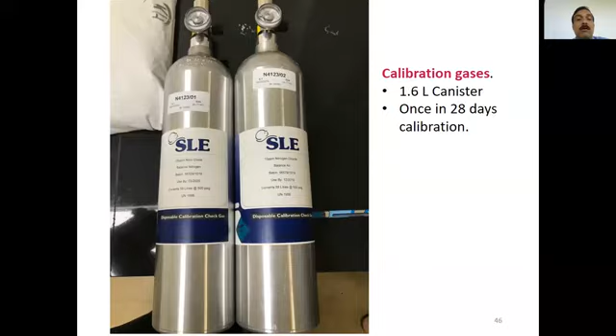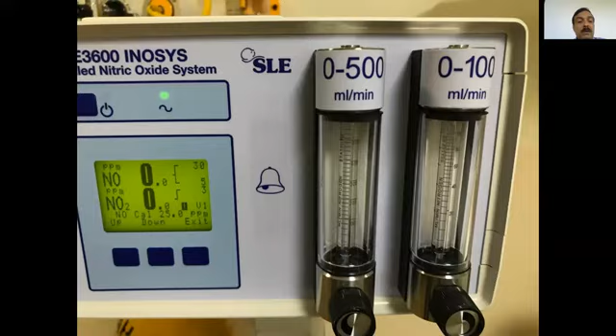And in this delivery system also, there are two systems, 0 to 100 ml and 0 to 500 ml per minute, where we can calculate approximately how much nitric oxide is delivered. But we need not do that, because it is automatically calibrated and displayed in this monitor.